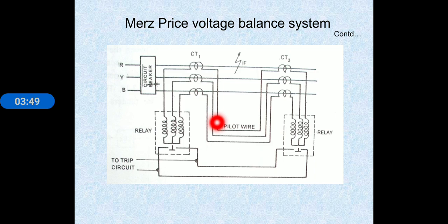But whenever a fault occurs, the secondary voltages become unequal. The entering current and leaving current become unequal, and the secondary voltages also become unequal. One side may have some value and the other side may increase. Suppose in current transformer 1 the secondary voltage is 5 volts, just assume like that, and in CT2 the voltage becomes 10 volts. The voltage is unequal, meaning the balance of the voltages is disturbed under faulty condition.